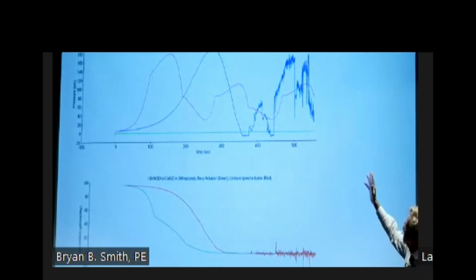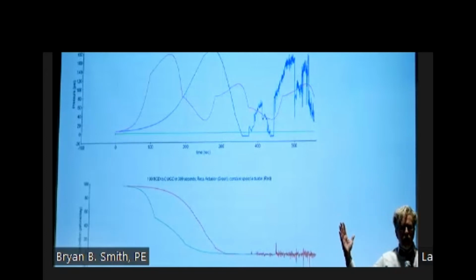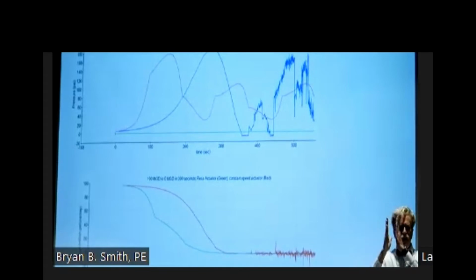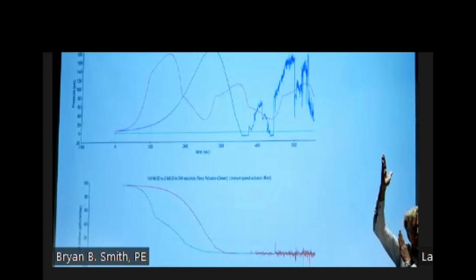You're like, oh, that's beautiful. Oh, you're still under 200 PSI. That's great. Except for when it closed, then remember, I'm closing the valve, I'm building up the pressure. Okay, the valve closed. I've gotten to that high pressure mark. Now what happens? Oh, shit.